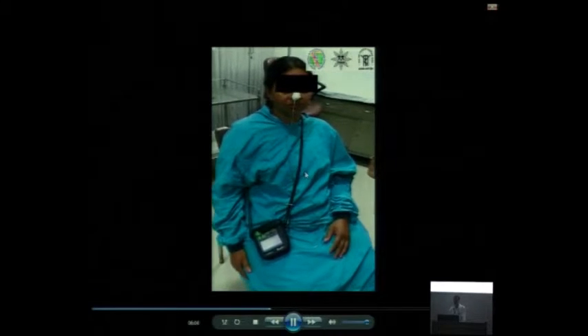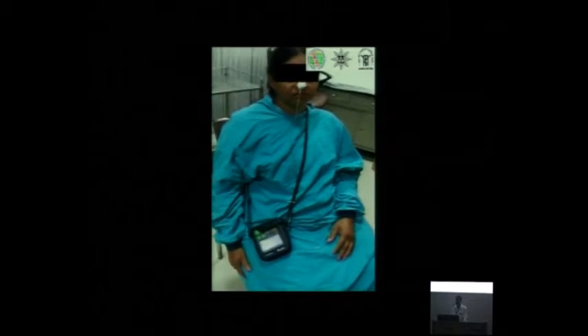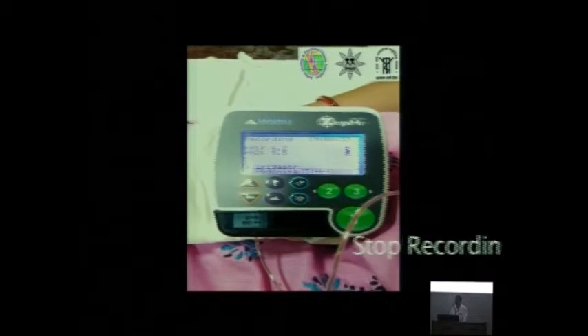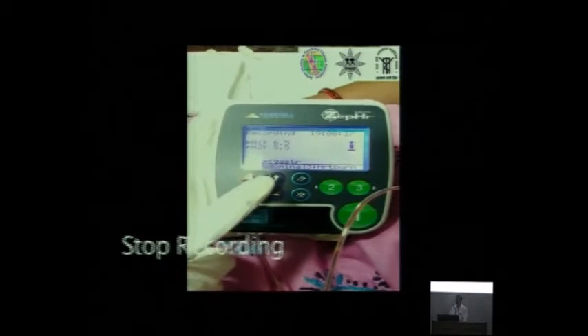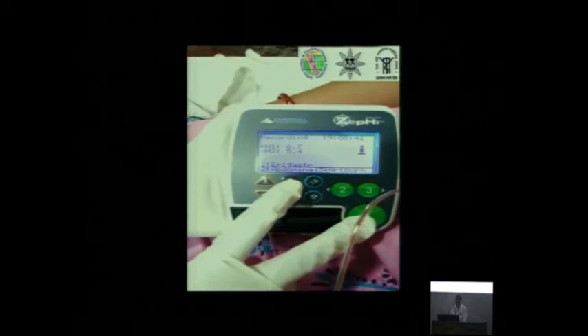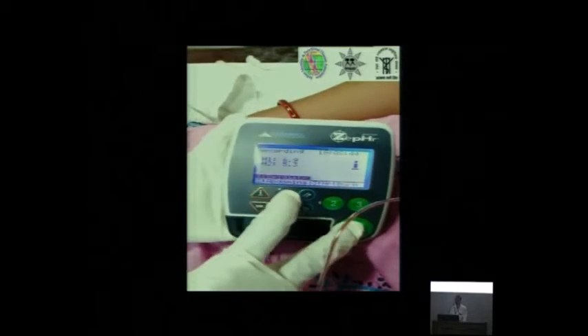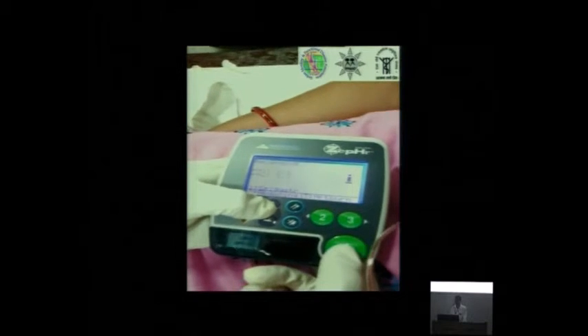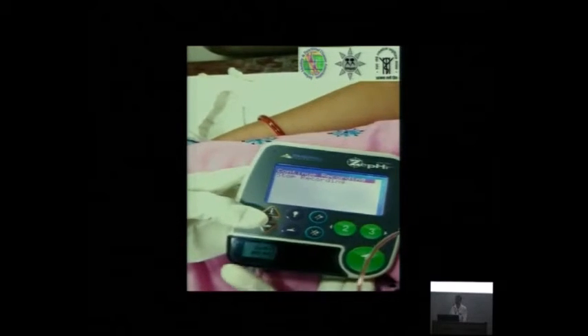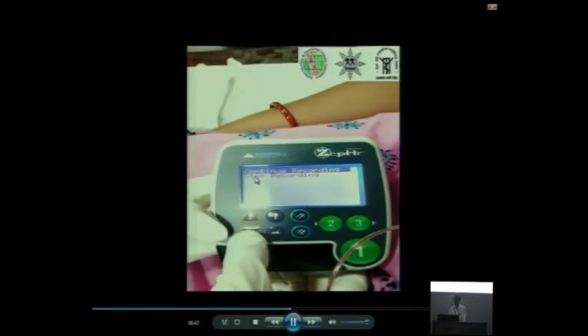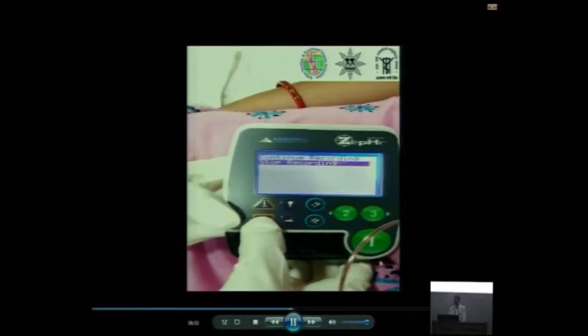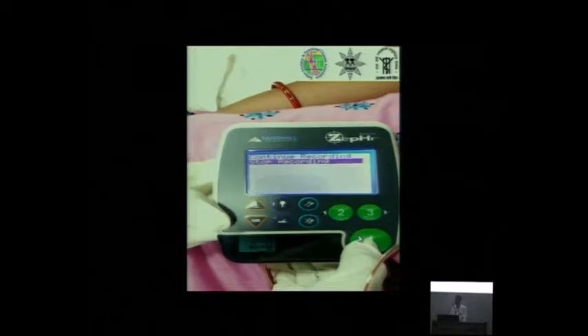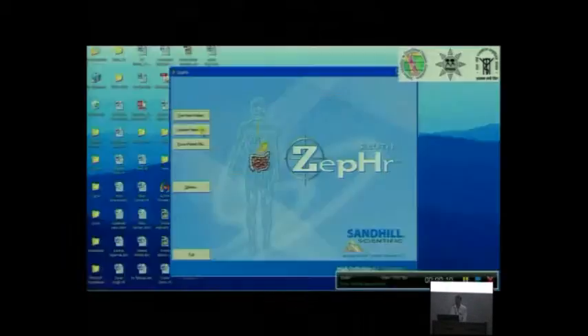Now what you do is fix this pH probe into the nose. Connect it to the data logger. Instruct the patient all the things - when she has to lie down what she has to press, when she has to have meal what she has to press, and all these. Subsequently, 24 hours later, you get back the recorder and you stop recording. By clicking on one and that bulb key you can stop recording. Both keys are clicked, then it says either continue recording or stop recording. Use this arrow key to come to stop recording. So arrow key is this lower one. Stop recording, then we'll enter one. One is the enter key. One is also event key and enter key.